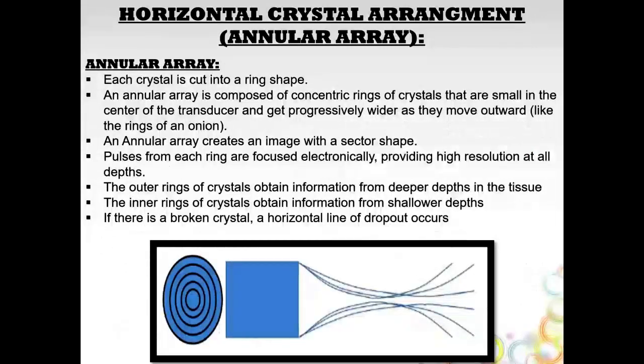Annular array. So this is our next type of transducer. This is where crystals are cut into a ring shape, and each ring is a crystal. Each ring fires a pulse, and these are concentric rings, so they're smaller in the center and then get bigger as they go outward, kind of like the rings of an onion. And this creates a sector-shaped image. The pulses from each transducer ring are focused electronically, so you get high resolution at all depths, and you don't get that beam divergence artifact. The outer rings fire and go deeper in the tissue, so they get information from deep depths. The inner rings fire more shallowly and you get information from shallower depths. Now, if you get a broken crystal, you get a line of dropout.